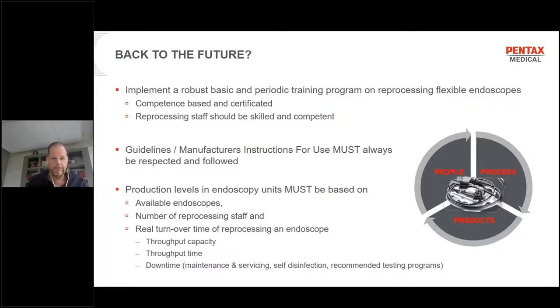The guidelines and manufacturers' instructions for use should always be respected and followed. No, they must always be respected and followed. Production levels in endoscopy units must be based on available endoscopes, the number of reprocessing staff, and the real turnover time of reprocessing an endoscope, the throughput capacity and throughput time, and even calculating the downtime needed for maintenance, servicing, self-disinfection, and increasingly important, the testing programs and microbiological sampling.